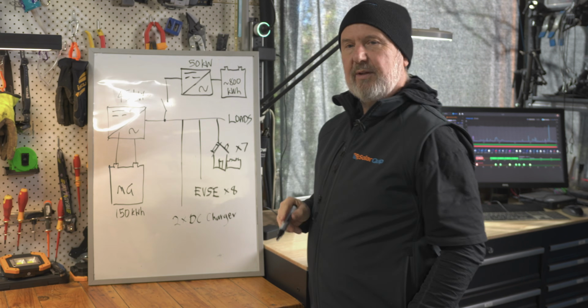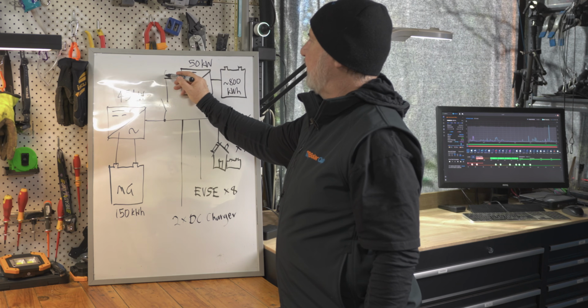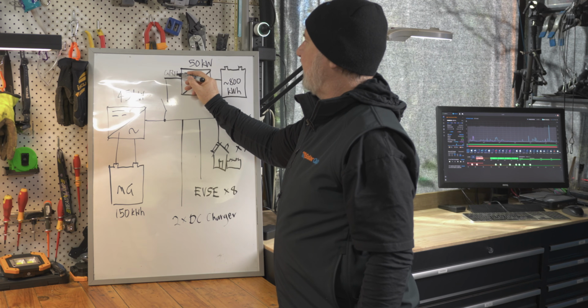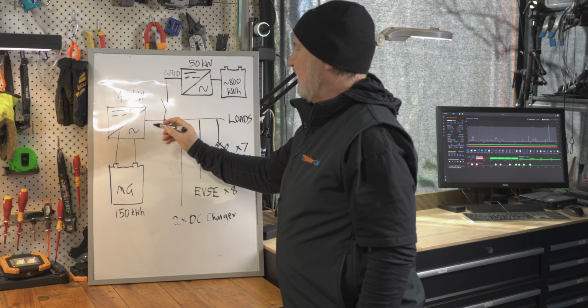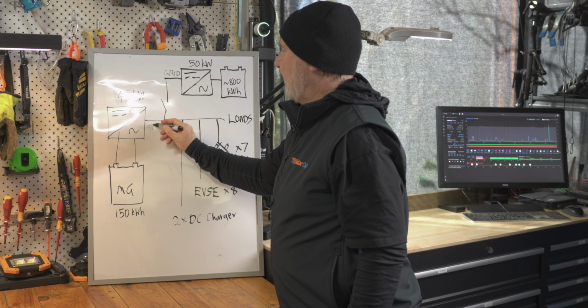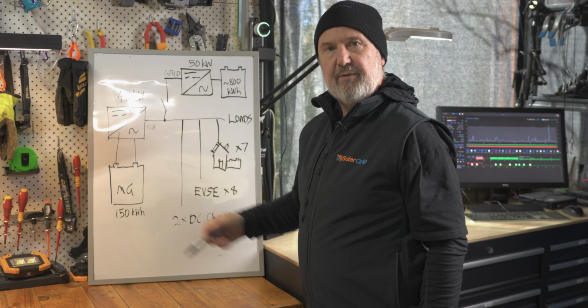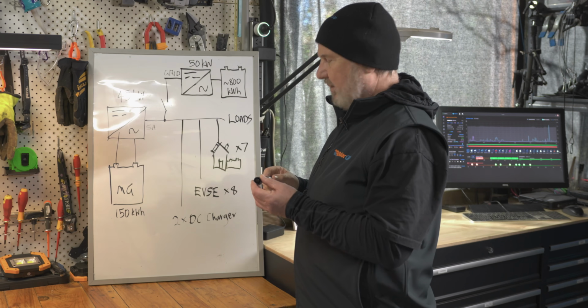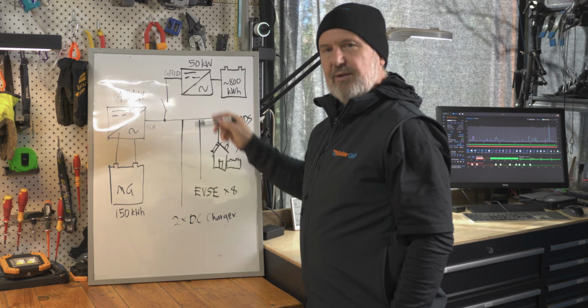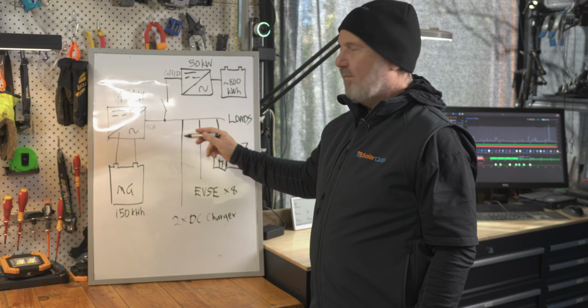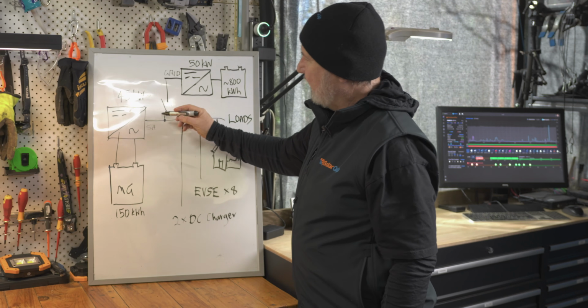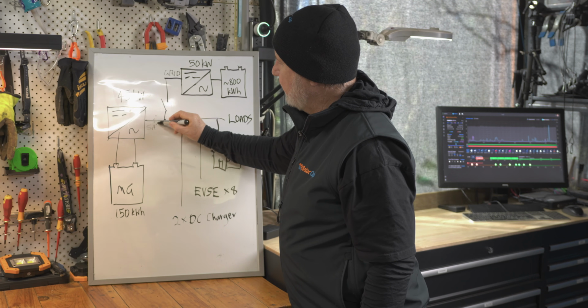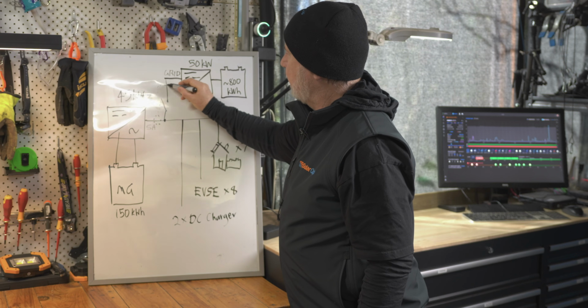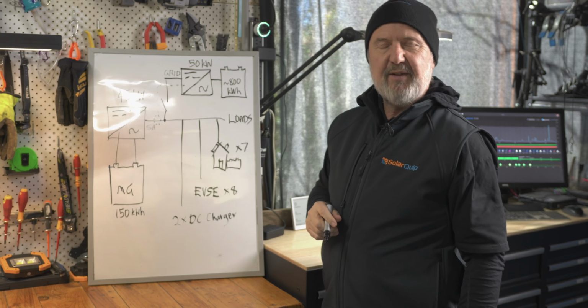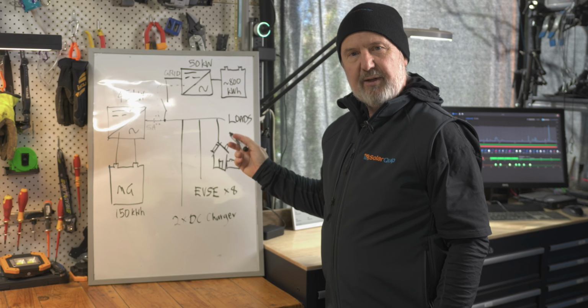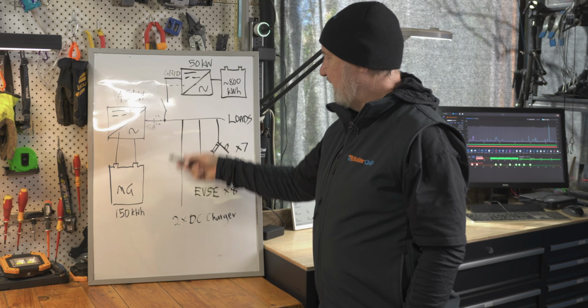But how does this work? Well, we've connected it to the grid port. So it's a hybrid inverter, so it has a grid port, whereas this is the standalone port, SA for short, of the grid forming system. And the way that this inverter knows how much to contribute is done with CTs. Basically, we've got a CT around here, and the CT measures the amount of energy flow that the microgrid is drawing, so all of these loads.